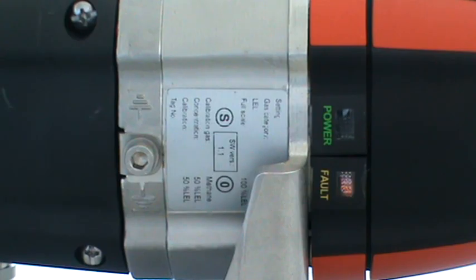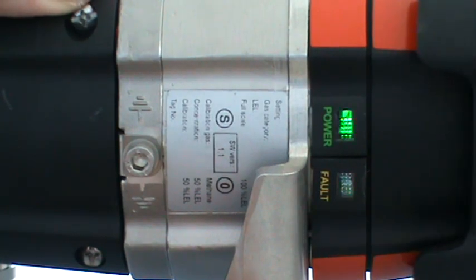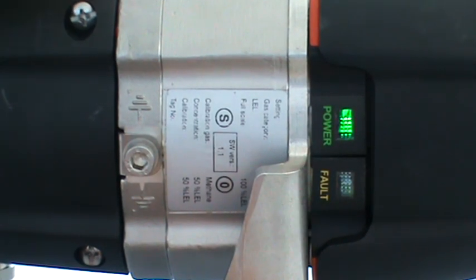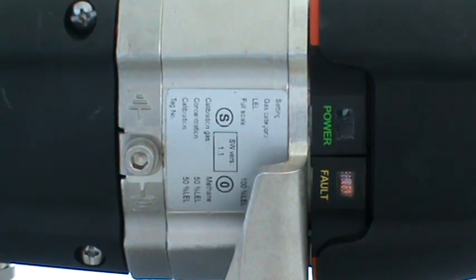Now we need to apply zero gas, nitrogen or synthetic air. And for that reason, I place the calibration adapter on top of the splash guard. And we start gassing the zero gas to the instrument. Here it is important to achieve a stable gas concentration inside the PIR 7000's measuring cuvette, and this takes typically 3 minutes. Then we can confirm the stable measuring value by hitting with the magnetic wand again on the 0 sign of the label, now in total for the 3rd time.